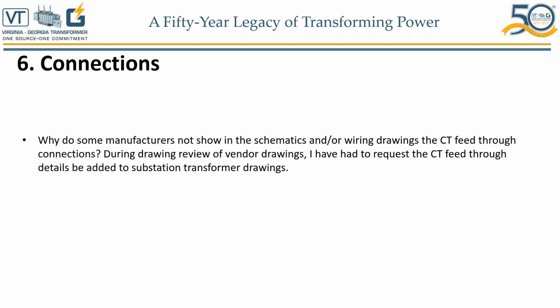Let me first explain for those who may not know what we're talking about here. First of all, CT stands for current transformer, and depending on what you're going to do with these CTs in the field, in the substation, for your protections and whatever else you want, we put the CTs that you want us to put in your transformer. Then we take the CTs, which can be mostly bushing mounted, inside the tank or outside the tank, depending on the application.